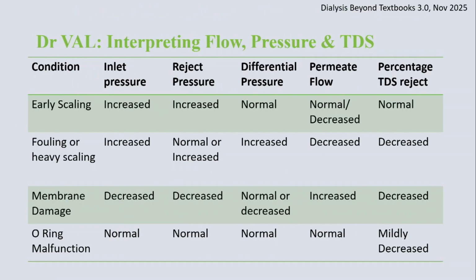Next. So how to interpret? Dr. Rajapurga talked about pressures. What we have is flow meters, pressure meters, and TDS meters on our control panel. And this is what you would find. Early scaling, the inlet pressure is increased, the reject pressure is increased, the TDS reject would be normal in such a situation, the differential pressure is normal. When you have fouling or heavy scaling, the differential pressure is increased because there is an increase in the inlet pressure more than the increase in the reject pressure, and the percentage TDS and the flow both are decreased.